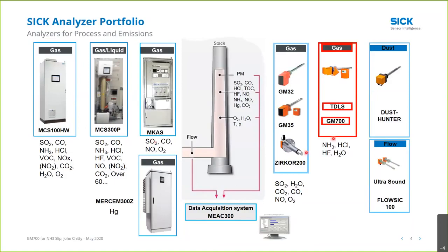And then on the right, we have in situ analyzers. The GM32 is for NOx and SO2 mainly. The GM35 is for CO, CO2, and water, infrared components. The GM32 is UV based. The ZIRKOR is for oxygen. It's zirconium oxide based. The topic today is the GM700 TDLS, tunable diode laser spectroscopy. It's an in situ gas analyzer for measuring ammonia, HCl, and hydrogen fluoride. We also have dust products for particulate monitoring and opacity. And we have a flow product for stacks and emissions monitoring as well using ultrasonic flow. So you can see here, SICK does a lot of applications around emissions monitoring, and SCRs are included in that.